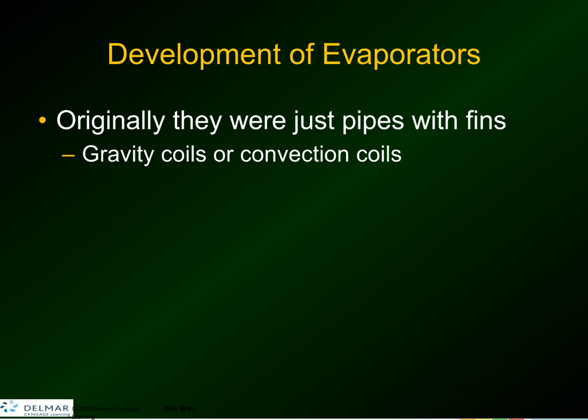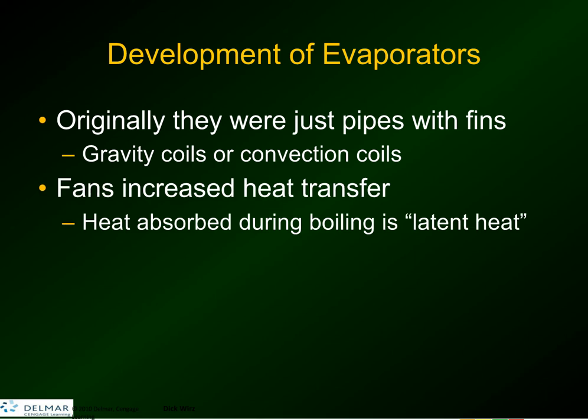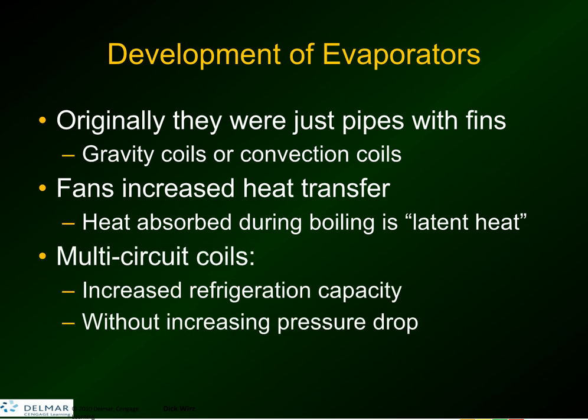Just a quick review of evaporators. Originally, they were just pipes with fins on them. I have seen older refrigeration systems with just pipes — especially for a pastry cooler that has just a pipe that gets cold and uses gravity and convection, with no fans whatsoever. Fans are used to increase heat transfer and move more heat across the coil rather than relying on convection. Multi-circuit coils were then developed to increase refrigeration capacity without increasing pressure drop.